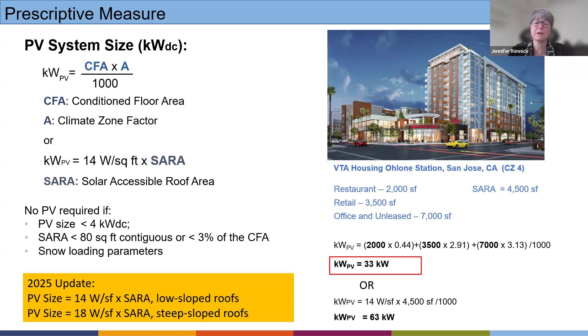Under the 2025 code update, that alternative based on SARA, the solar accessible roof area, has changed a little bit. So it's still 14 watts per square foot if you're on a low slope roof, but they've added an 18 watt per square foot requirement for steep sloped roofs. Otherwise, the section's pretty much the same. And it's still true that if you have a mixed occupancy, then you would apply this formula to each of the occupancy types and add it together. And there are some exceptions if you have a tenant space that's completely separate. It's a little nuanced, but that's the basic idea.